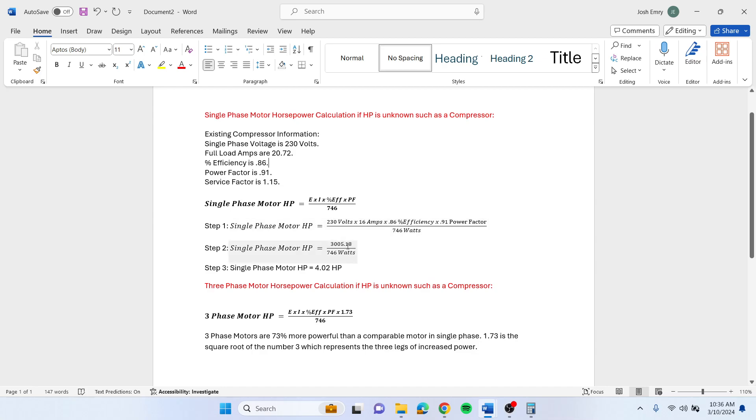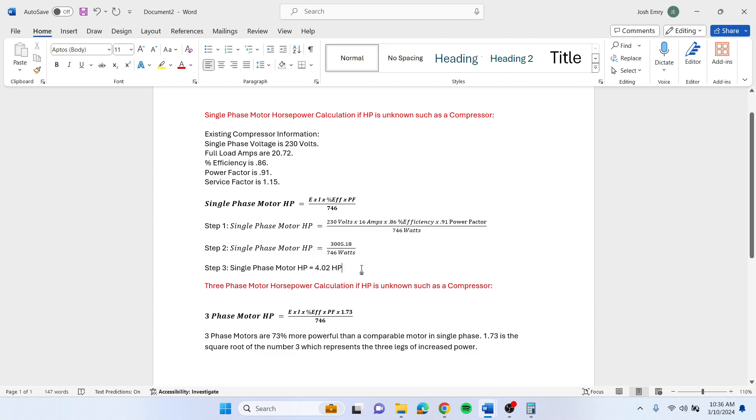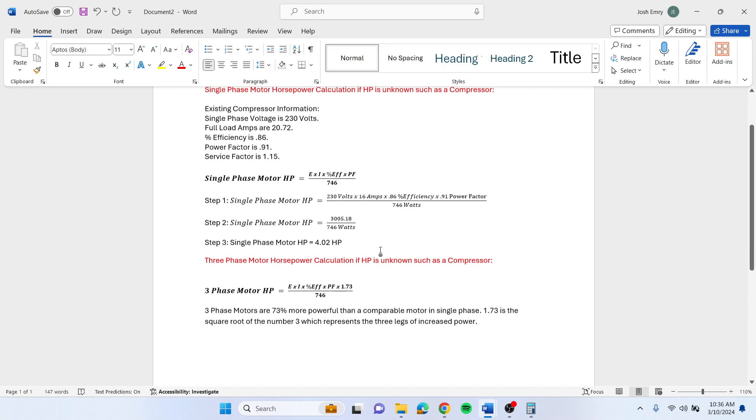You end up with 3,005.18, and then you divide by 746 watts. So right now that motor is running at 4.02 horsepower. If it's close to full load amps, then it's probably a 5 horsepower compressor.